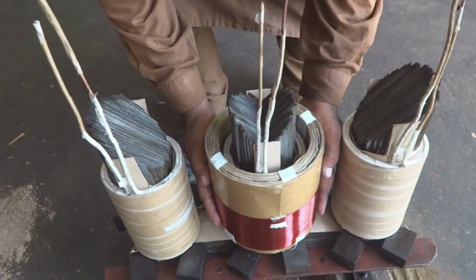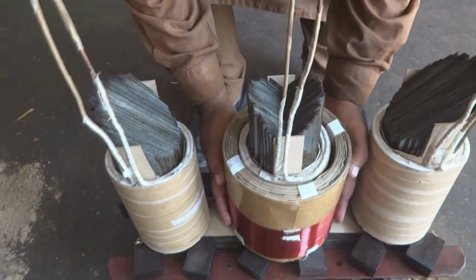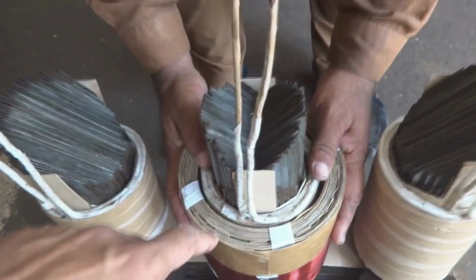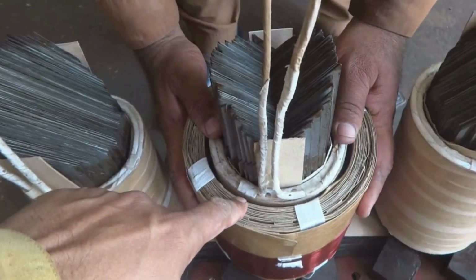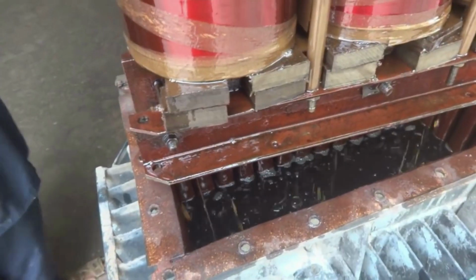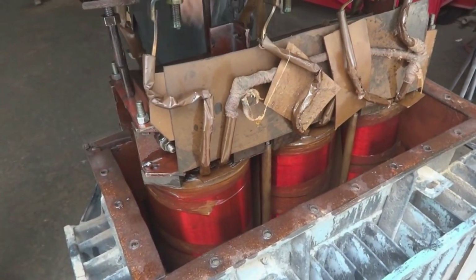This can be generalized for electrical equipment and systems, for the generator, for the electric motor, and for the distribution transformer, oil-filled distribution transformer. We saw how this transformer was manufactured step by step and how the insulation materials are used in this transformer. Starting from the windings themselves, whether the low voltage or the high voltage, wires or copper foils, they are themselves insulated, also separated by insulator, papers and woods, and they are inside the tank immersed in the oil. Oil will provide more insulation resistance required for this transformer.